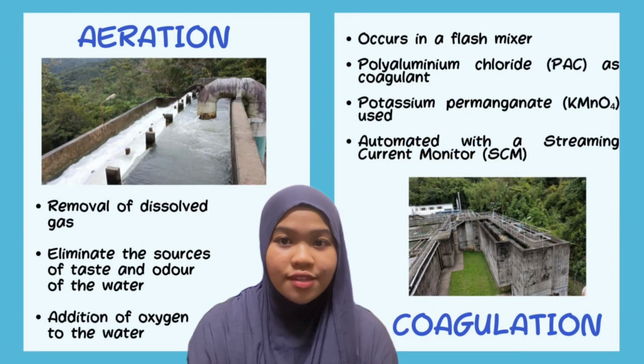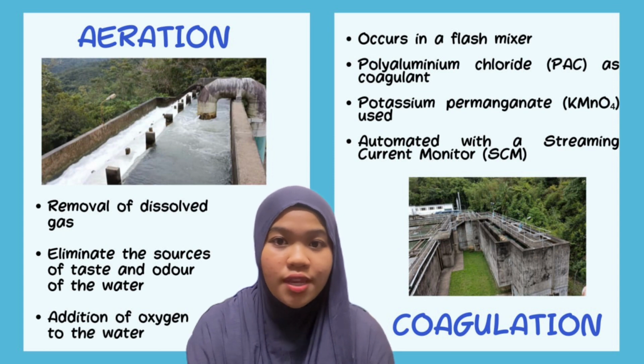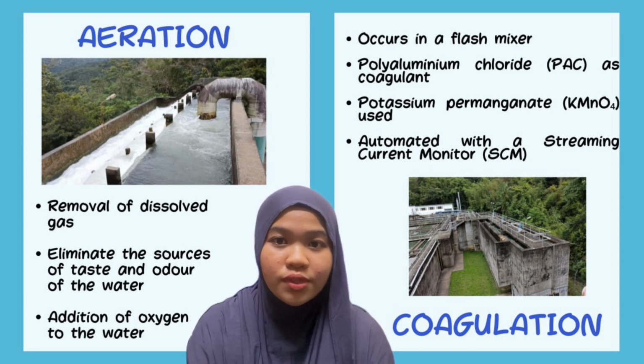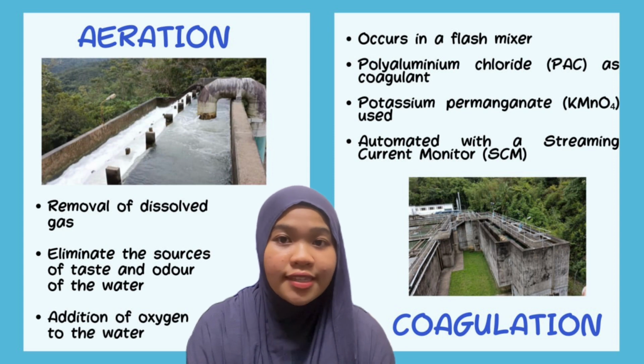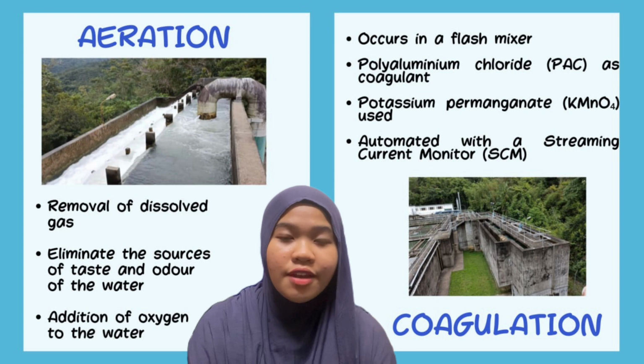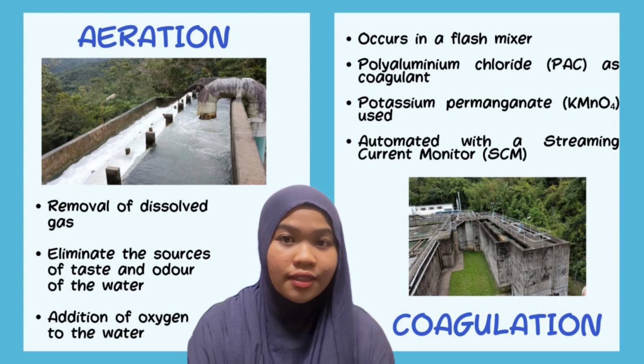Next, the aeration process removes dissolved gas and oxidizes dissolved metals like CO2, iron, manganese, and H2S, reducing unpleasant taste and odor in water. It converts metals from soluble to insoluble states, resulting in precipitate that can be removed through sedimentation or filtration. Cascade aeration is an excellent option using natural draft units, increasing oxygen levels in water by 30% at each stage.